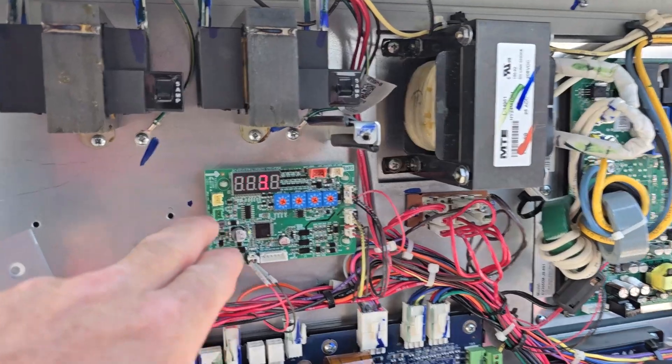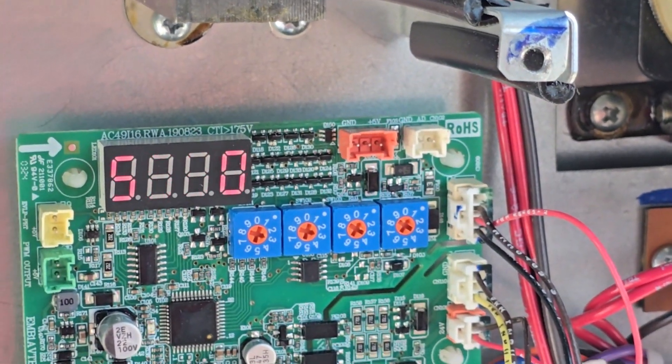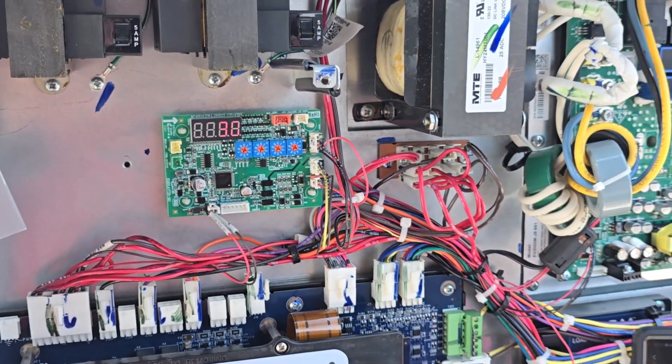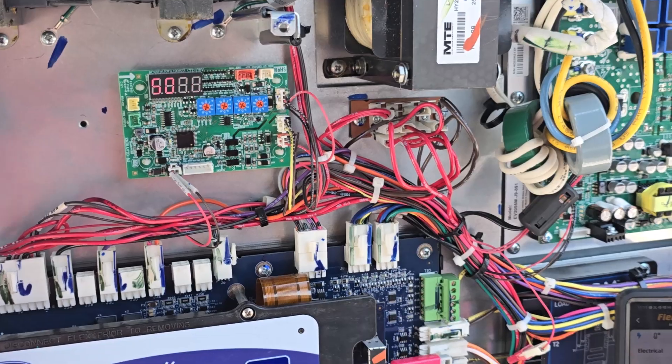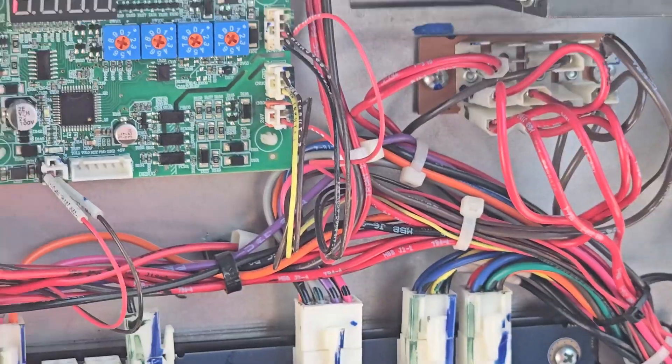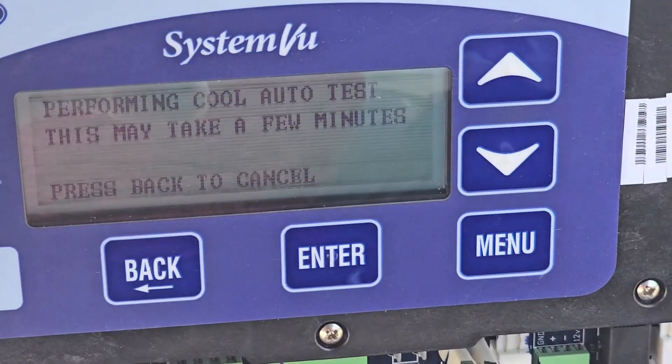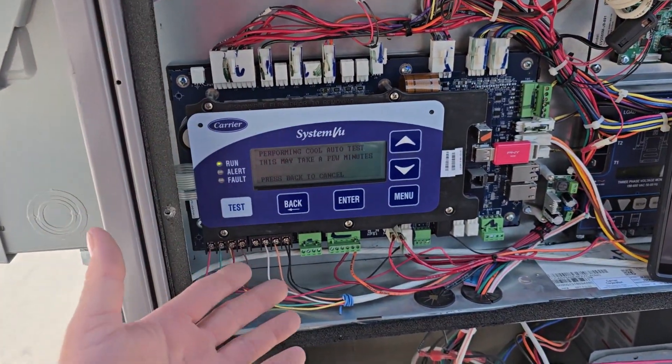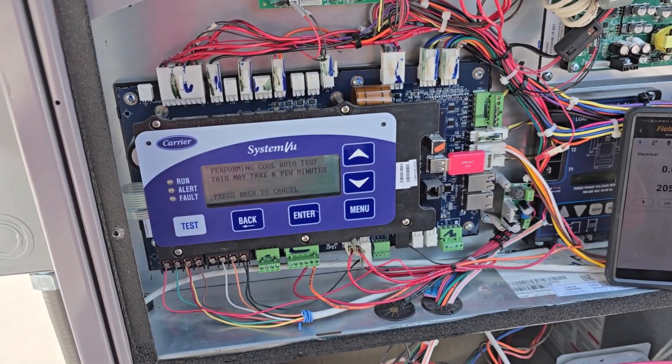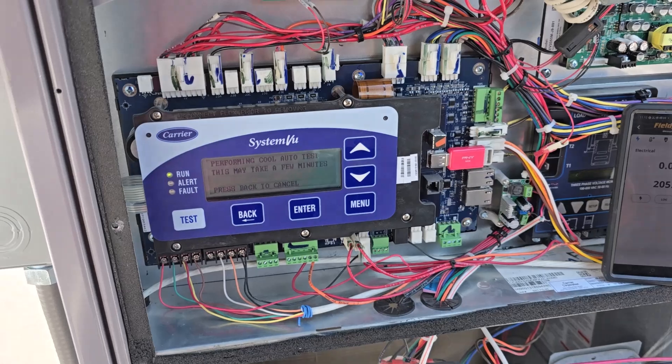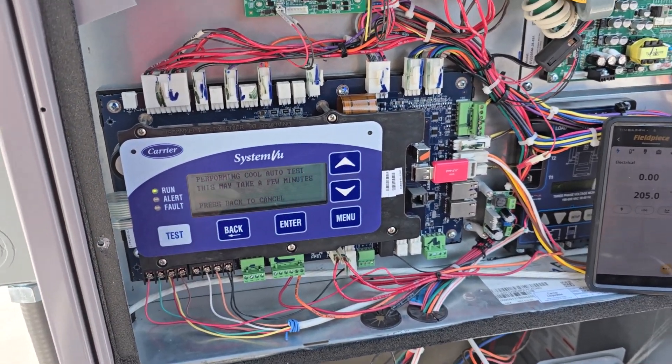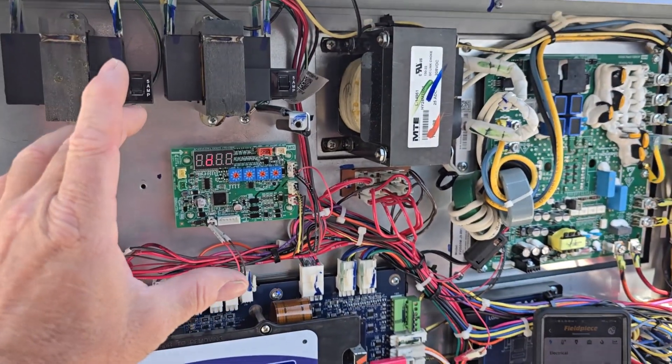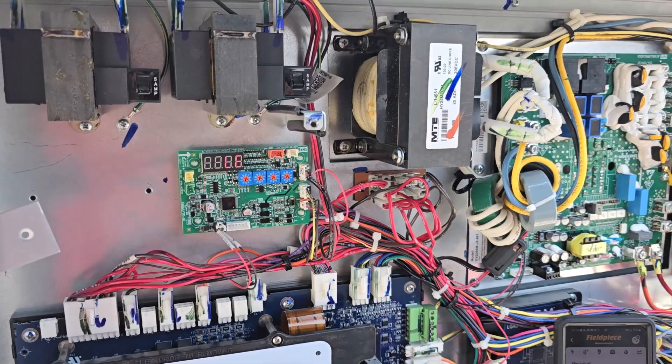It also tells you if it's idle like it is now, idle, and I can't see that very well, or the RPMs. Or if it faults, it'll read the fault code like E-14, E-19, something like that. So that's what you got. So this will tell you that the cooling failed because it calls for cooling. And then after a few minutes, it notices that the suction pressure transducer did not show that it was pumping. And then it'll say failed to pressurize in your faults. Other than that, you got to go to the Emerson converter board here, check for faults up there.